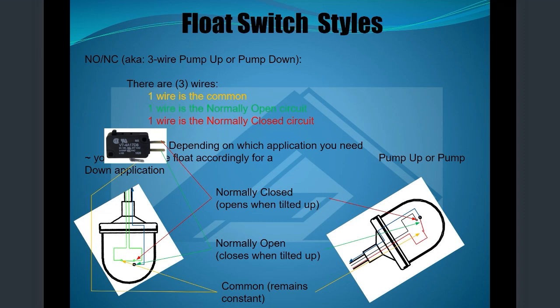All right, so here is our 3-wire switch. So I'm gonna get a little closer here. On the bottom left here, you have a couple different circuits, and this circuit is your common wire. So that one is connected to one of your wires coming out of the backside of your float. And there's a little lever here that either touches this contact or this contact. When it's touching this contact, you can use both of these wires, and as it's hanging down, it's gonna be normally closed. But if you use your common wire and your outside blue wire, as it's hanging down, it's gonna be normally open, because that circuit is open. And then as it tips up, that lever or switch in there goes from the top contact down to the other one. So depending on which wire you use, you can actually just stock one float in your truck and use it for either application.